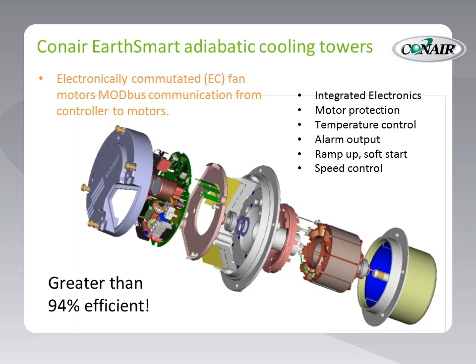Electronically commutated EC fan motors provide variable frequency type efficiency with even more control in an integrated package. Modbus communication from the unit controller to each motor in the system ensures precise control and performance. Soft start and ice breaker modes protect fan blade integrity and provide long life. In the unlikely event of a failure, the entire assembly is replaced as a unit — no gear pullers, fan balancing, or belt tensioning is ever required.